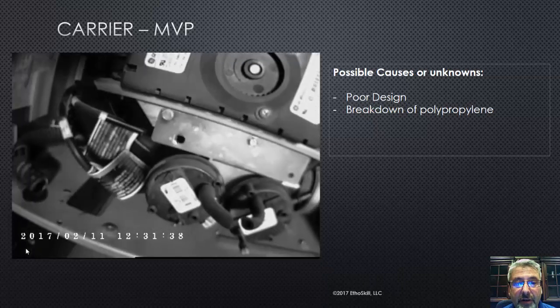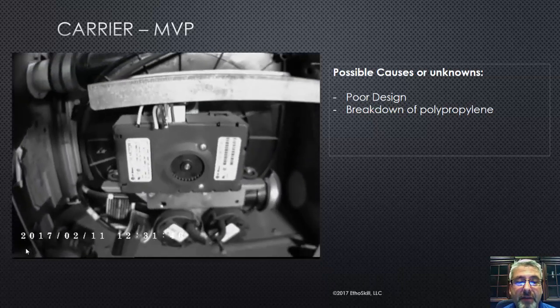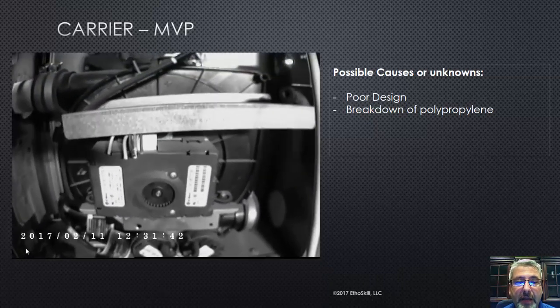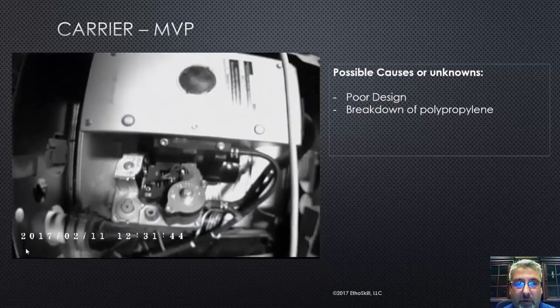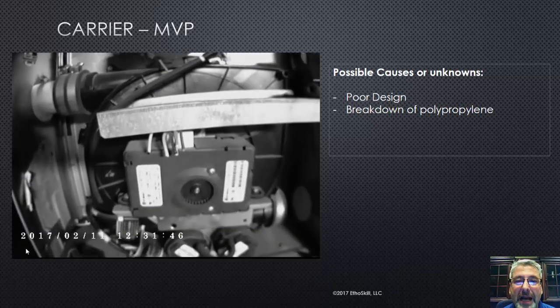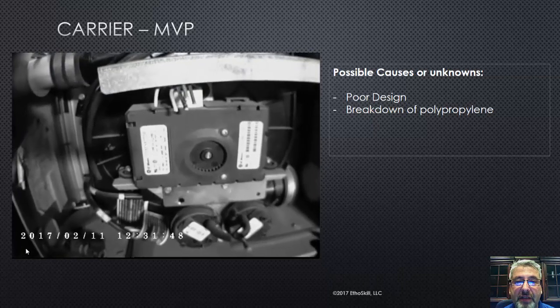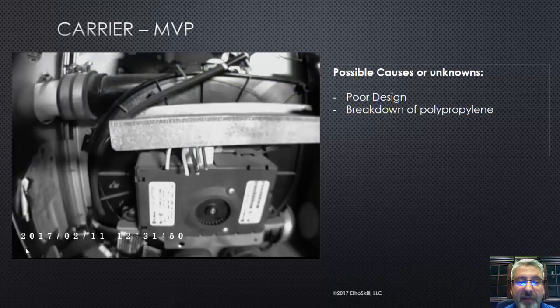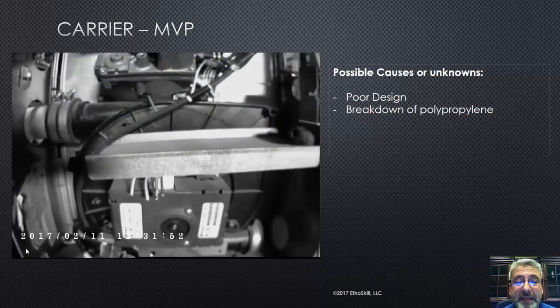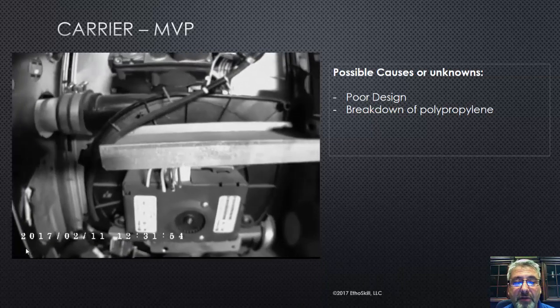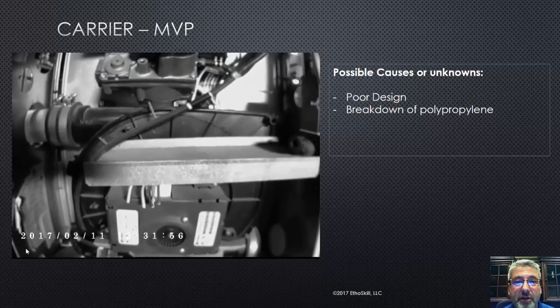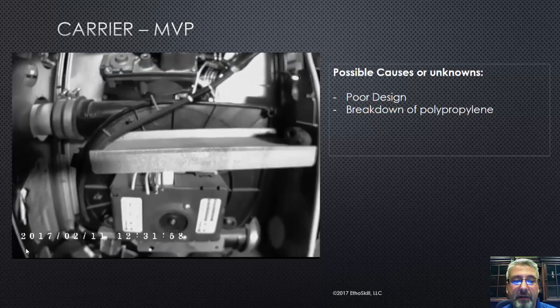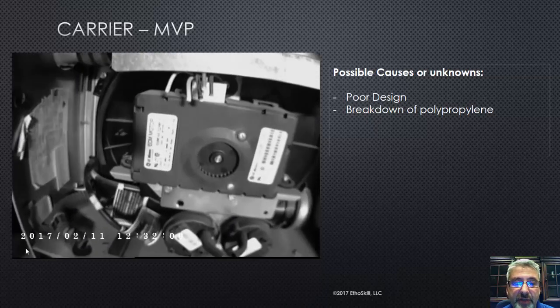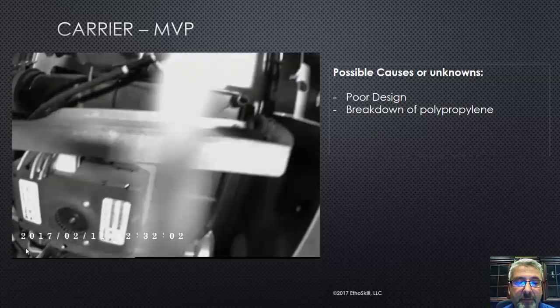There's the vent motor. Now, for you techs, if you ever see a rectangular vent motor like that, that's an ECM vent motor. The round ones are the non-ECM, they're actually PSC, and most of them have a little 3 microfarad capacitor. But that's an ECM vent motor, so the minute you take the door off this furnace, you know immediately that this is a 2-stage variable speed gas furnace. That's not the purpose of this portion of the video though.